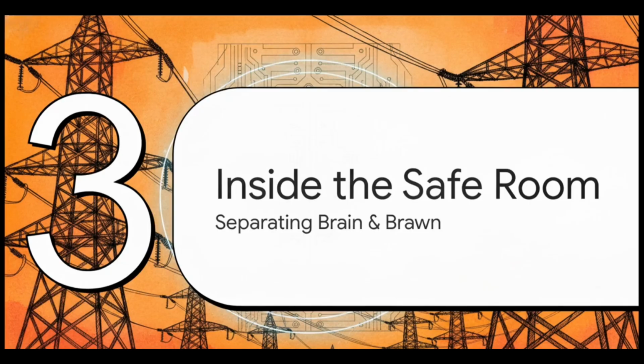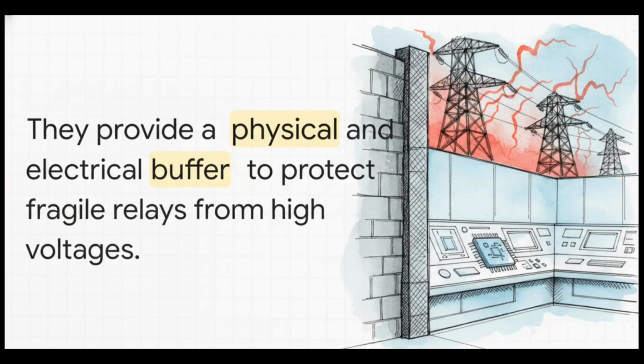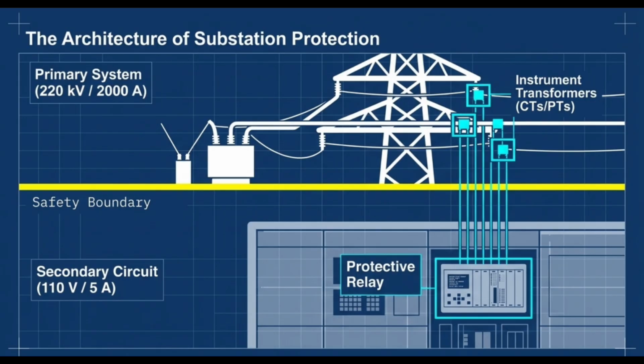Which brings us to Section 3, inside the safe room, separating the brain from the brawn. Look, these modern microprocessors, they are brilliant, but they are delicate. You absolutely cannot just bolt them onto a live, high-voltage power line. Physically, they're mounted on relay panels inside substation control rooms or integrated into switchgear cubicles. They're kept far, far away from the lethal energy of the actual transmission lines. They require a very strict physical and electrical buffer, living entirely in a secondary low-voltage control circuit.